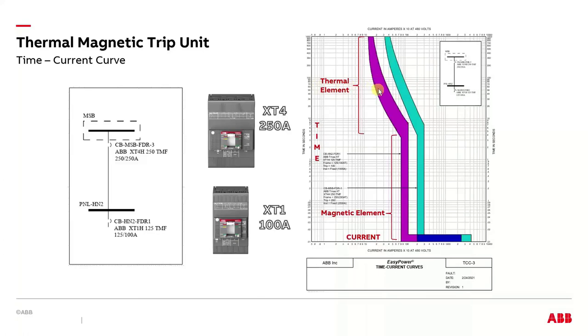And there's some significant difference in time because this time scale here is a log, and this is a log. So this time here is a lot longer than this time here would be. So for example, if you're at 200 amps, it's going to trip between 40 seconds and 200 seconds. So you can see that's a pretty wide band. This is your thermal component of the breaker, this curved part. And then the bottom, that's your magnetic element. So you can see that the bottom magnetic element is not going to do anything until it reaches its pickup value. And whenever it does, it's going to trip right away. So that's your instantaneous protection, and your thermal is your overload protection.